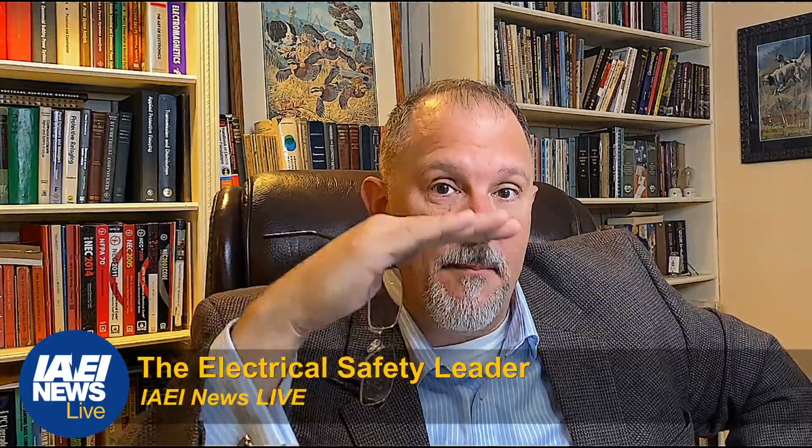And it says, or a permanently installed metering device in the equipment for indication. So one of the discussions that they had about this capacitive test instrument and the concerns was that on some of these medium voltage applications, you can have a lower voltage that capacitive sensor won't measure. So understand the limitations of the capacitive test instrument that you are using. Understand that there might be a bottom threshold to where there is a voltage higher than 50 volts present that device may not be able to detect.